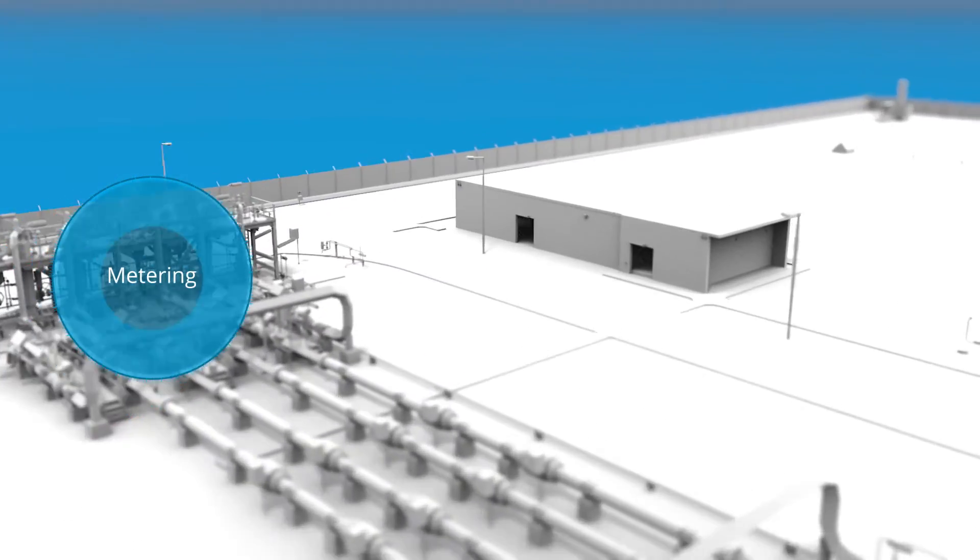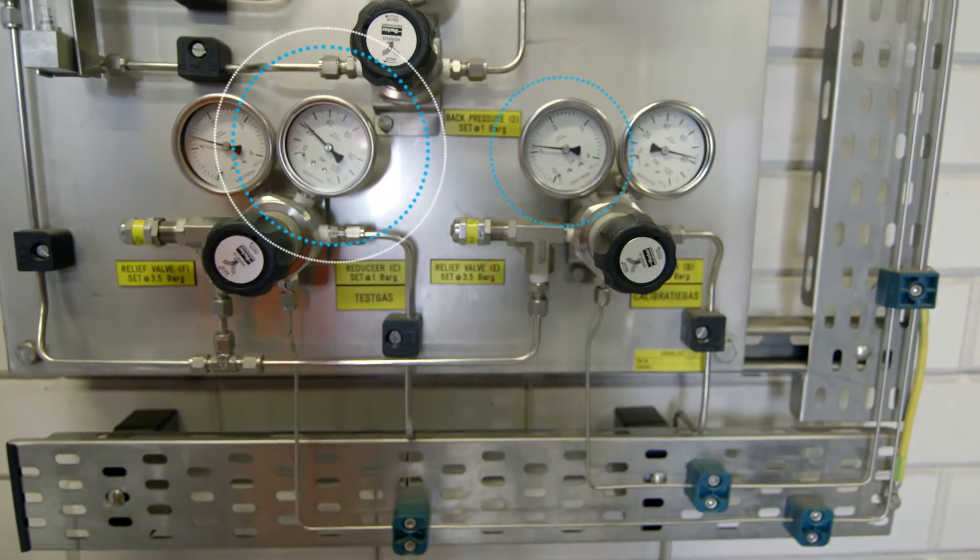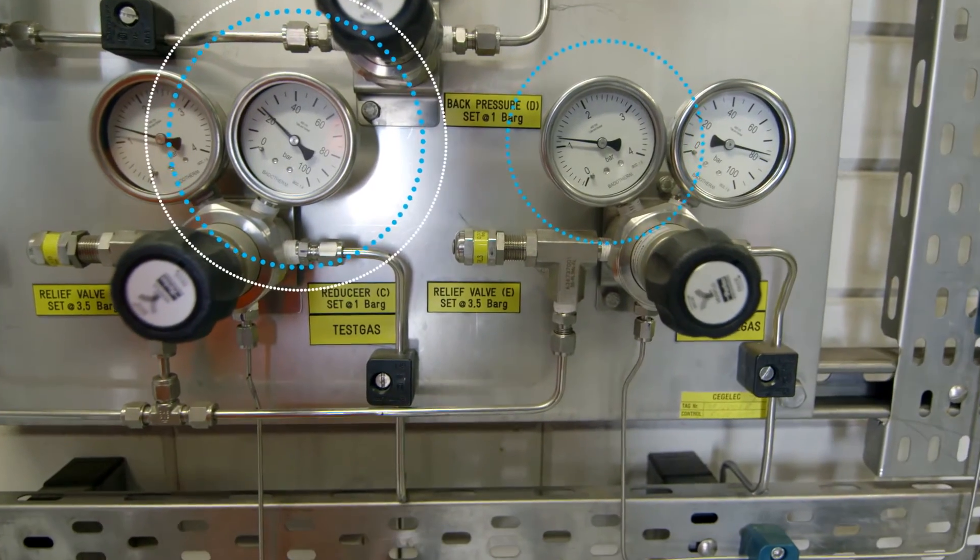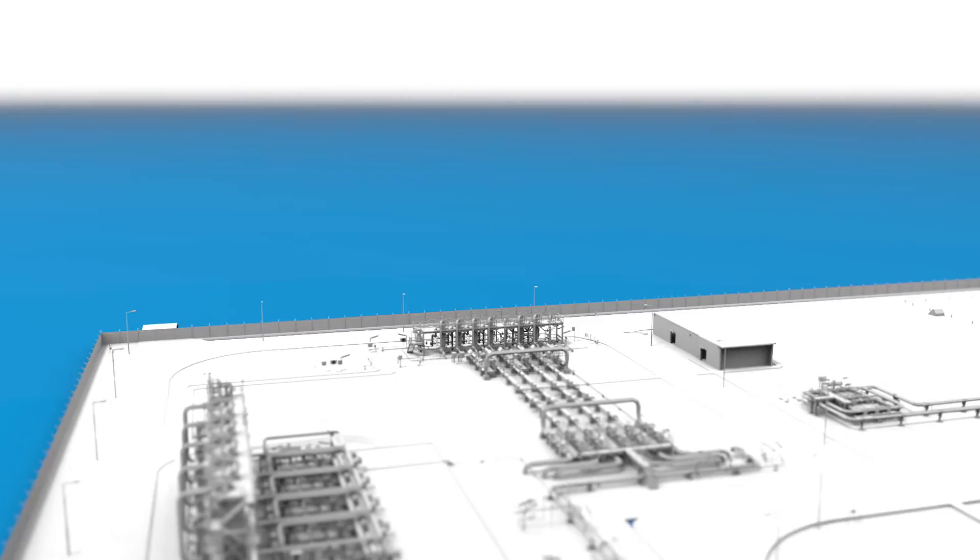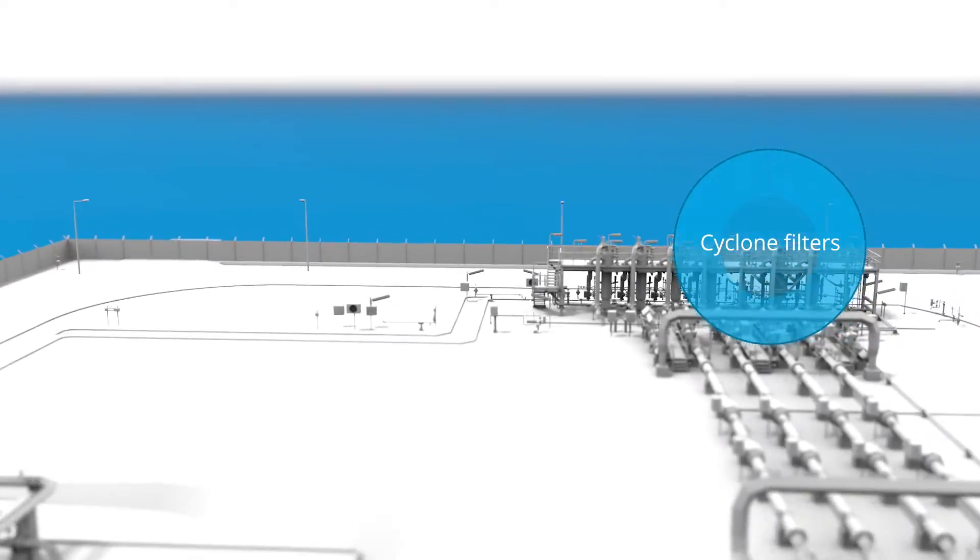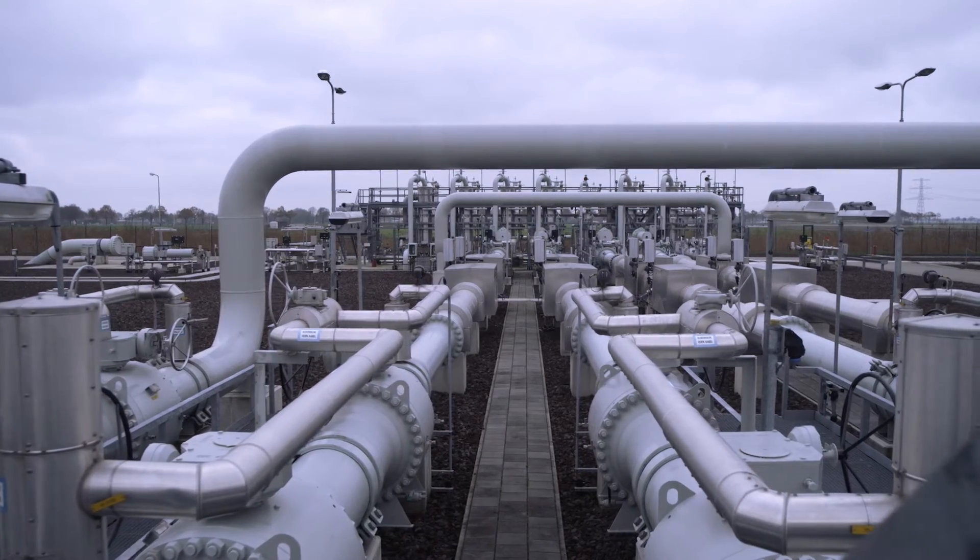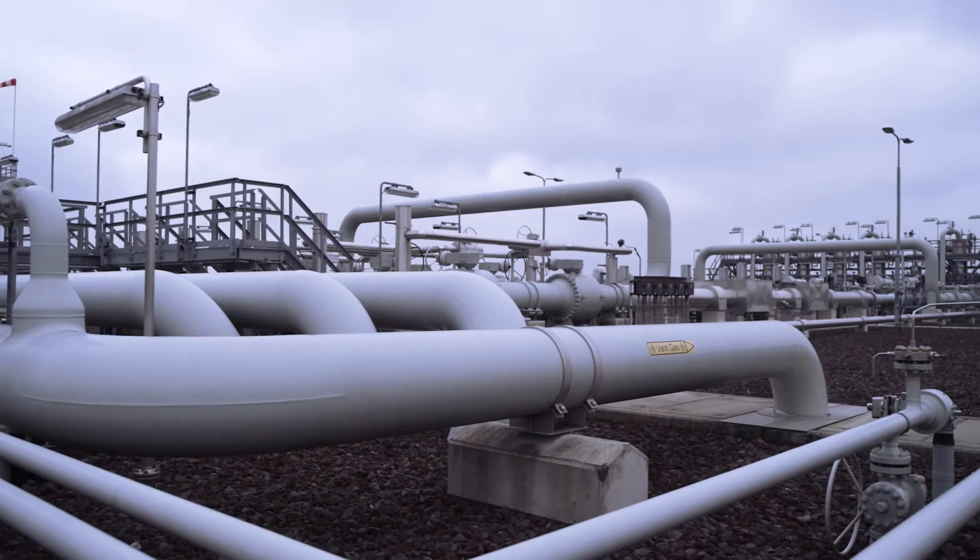The gas flows are measured during both injection and withdrawal. This allows to determine precisely how much gas is being injected into the caverns and how much is being supplied to the transmission network. Before the gas is measured, it is cleaned by cyclone filters to prevent any small particles which may be present from contaminating the installation.